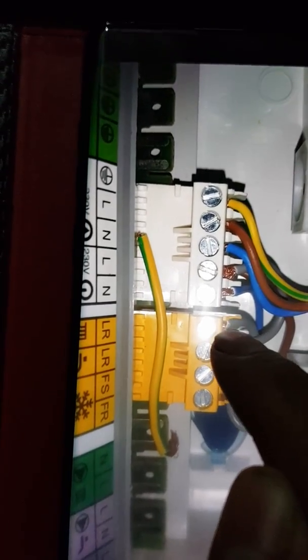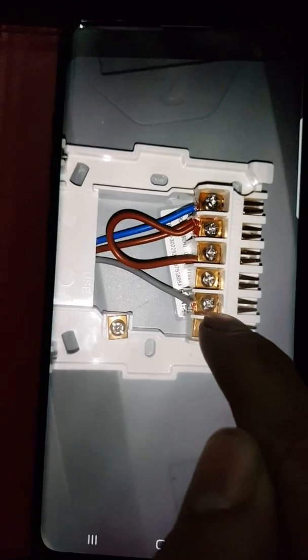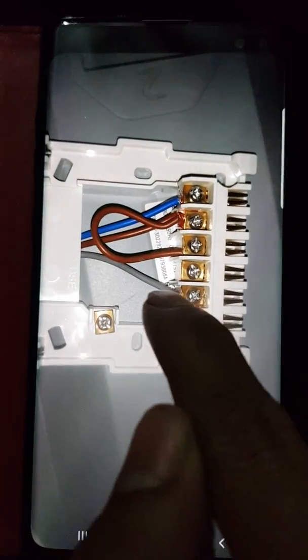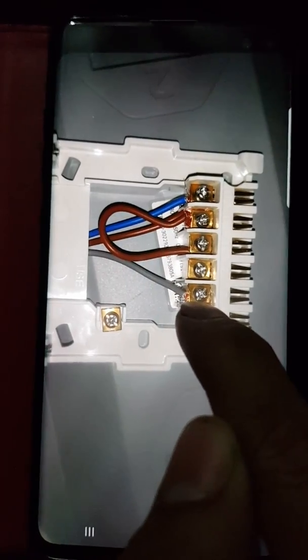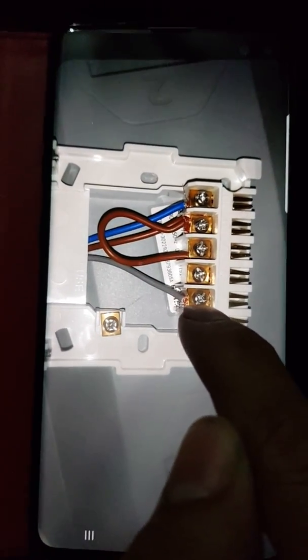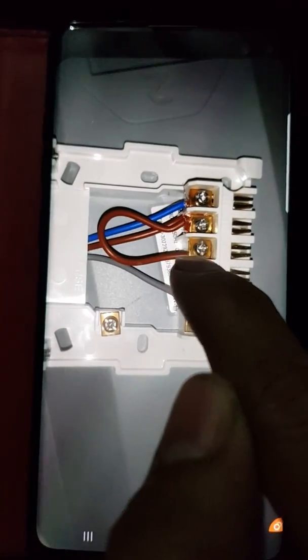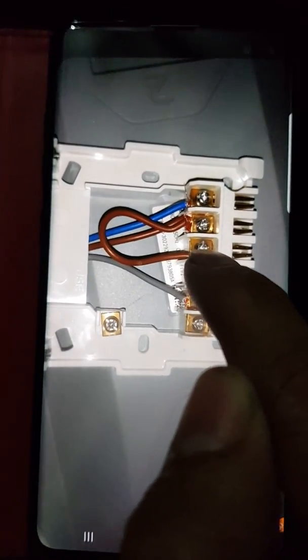This other gray one is for your heating, it's got a heating symbol — that's LR. That is going to come into number three, which is for heating on. As you can see in the diagram, you're going to need a link between live and number one, which is for common.